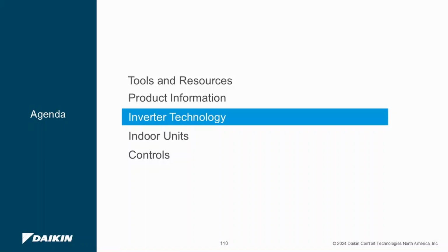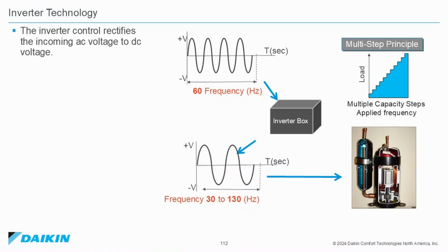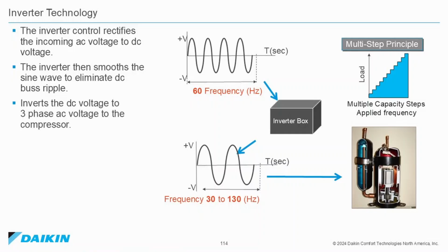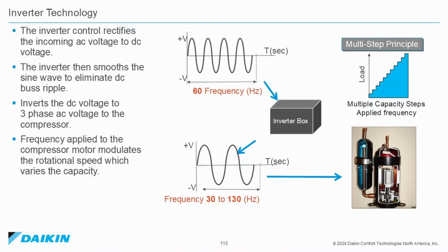Inverter technology. The inverter control rectifies incoming AC voltage to DC voltage. The inverter then smooths out the sine wave to eliminate DC bus ripple. Inverts the DC voltage to three-phase AC voltage to the compressor. Frequency applied to the compressor motor modulates the rotation speed, which varies the capacity. So the inverter takes the 208, 230 volt, 60 Hz incoming power and converts it to a variable voltage and variable frequency between 30 and 130 Hz to control the capacity of the compressor through multiple capacity steps, applied frequency depending on the load of the space.